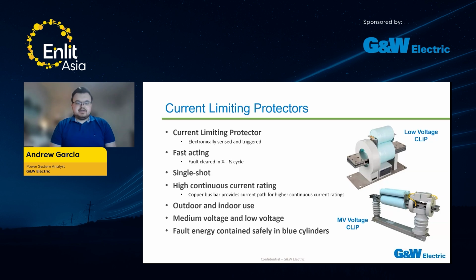Once again, these go up to very high ratings. They're single shot devices, meaning that every time there's a fault, you have to replace the blue cylinders that you see on the images to the right. We go up to very high continuous current rating, because it's just a copper bus bar in normal operation, so we can go up to 5,000 amps continuous with these devices, which is unparalleled in terms of providing a device when you compare this to current limiting fuses and solid state breakers. They are outdoor and indoor rated by default, so you don't need to worry about where to install them. Medium voltage and low voltage goes up to 38 kV.